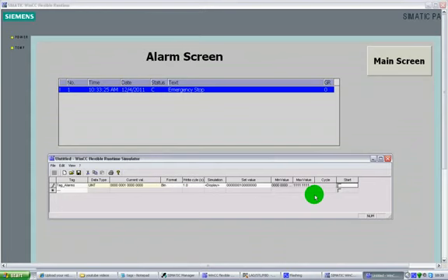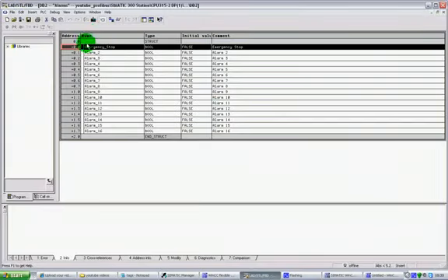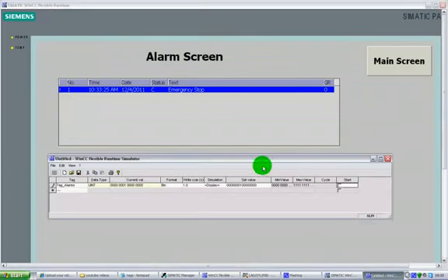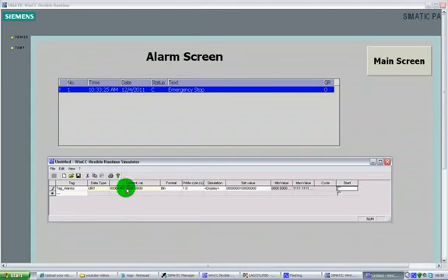It gets a little confusing, and because of this I will make another video on words and the structure of the words of Siemens, because it does get a little confusing when you're looking at it from the WinCC perspective to the data block perspective. Okay, because they do it in a column 0 downwards, and actually in the WinCC they do it as word 0 and then from left to right, and then the bits go right to left, so be very, very careful on those.